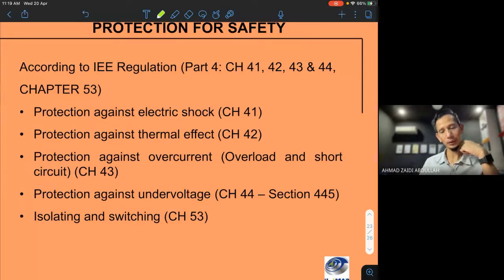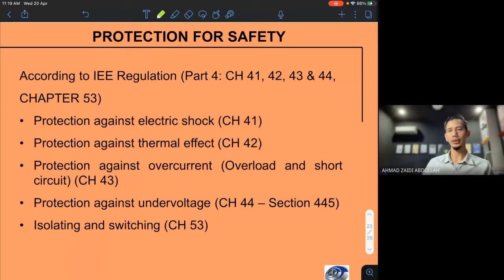According to the IEE regulations, you can open the regulations that I already shared with you. Part 4, chapters 41, 42 until 53. That book has detailed explanations on protection against electric shock, against thermal effects, against overcurrent, undervoltage, and isolation and switching. So try to read it, try to understand it. Why does protection for safety include that part? Please understand it, because this is the main contribution of the protection.